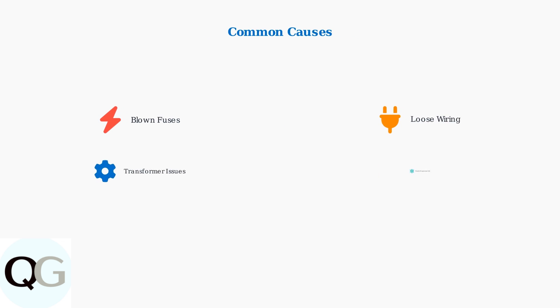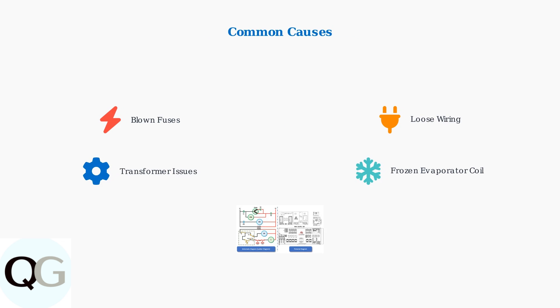Error code 126 can be caused by several issues. The most common causes include blown fuses in the system, loose or damaged wiring connections, problems with the outdoor transformer, or a frozen evaporator coil that triggers a low temperature lockout.